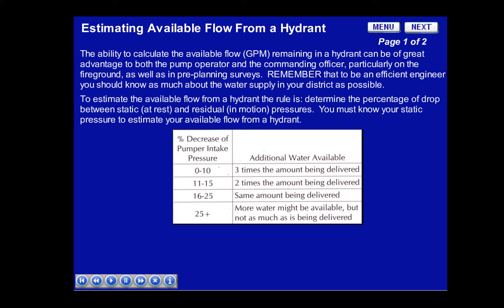This chart shows additional water available using the percentage of loss from the intake pressure. For instance, if you have a 10% or less loss — which is the difference between the static and residual pressure — you'll be able to supply three more like volumes as the original line. If you have a loss of 11 to 15%, you will only be able to allow for two more like volumes. And if you have a loss between 16 and 25%, you'll be able to deliver the same amount of water through your original line. If you have a loss greater than 25%, more water might be available, but not as much as being delivered.